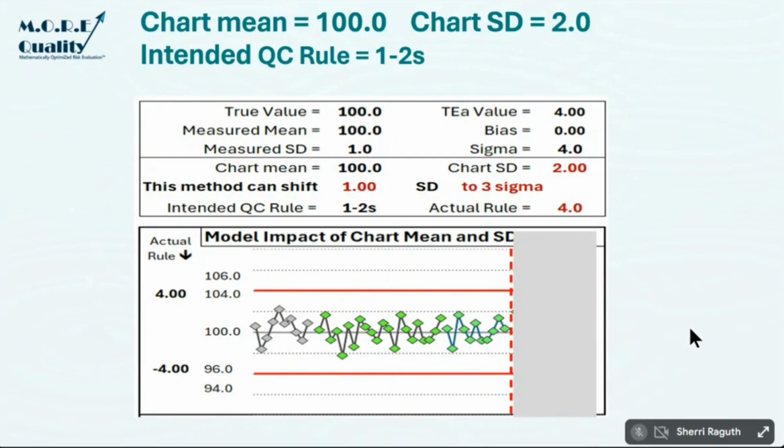It tells you you've got a problem with accuracy, you've got a problem with precision, you need to take this action or this action. This is the number of patients you're exposing to risk. If you do this, you will reduce it to your acceptable level. It's too complicated. You cannot manage risk with an Excel file. It's impossible. Once I upgraded from statistical QC to risk management, I needed to go to software. So it looks like what I'm using is Excel, but boy, this is Excel on steroids, and it's really being done in the software that's behind it.